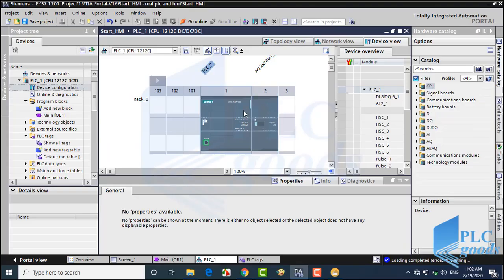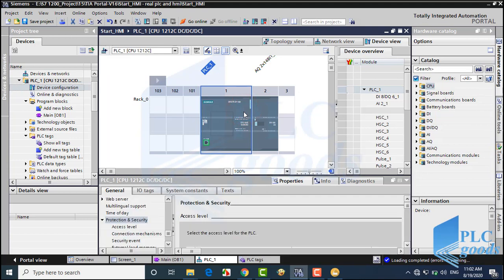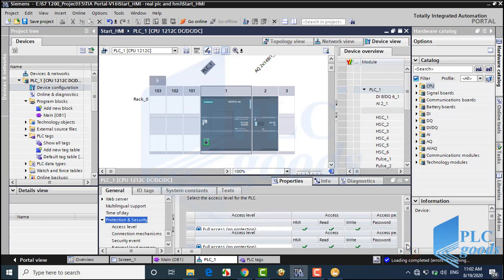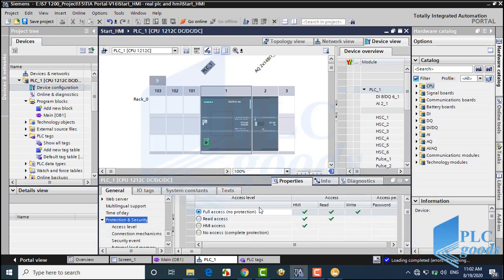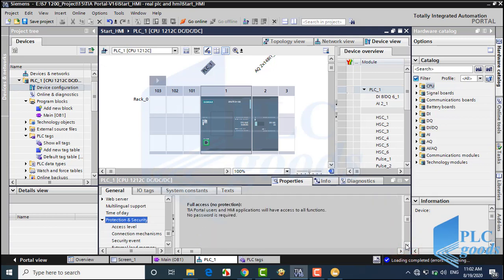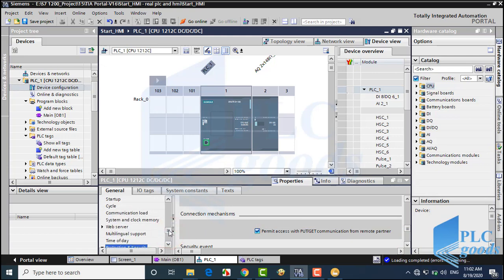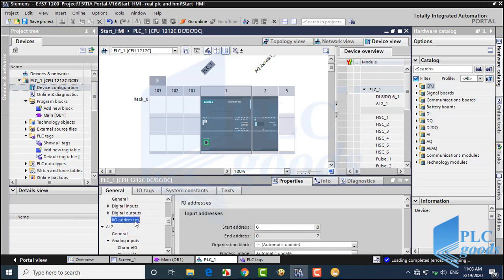First, we have to configure our PLC in TIA software. Then, to make a connection between our PLC and Factory IO, in the protection settings we need to have full access and permit access with PUT/GET communications from remote partners. Also, let me change the start address of my PLC input addresses from 0 to 10.